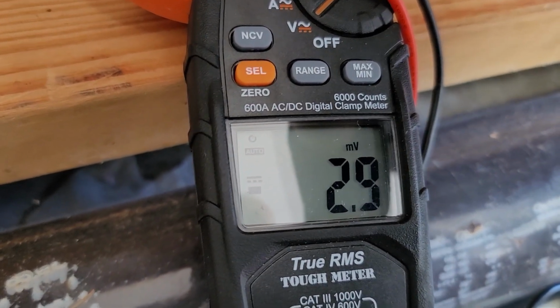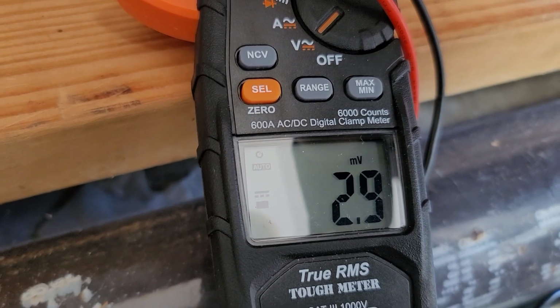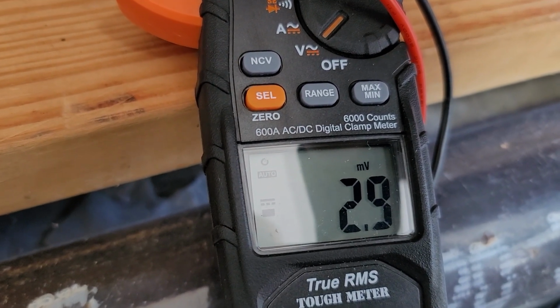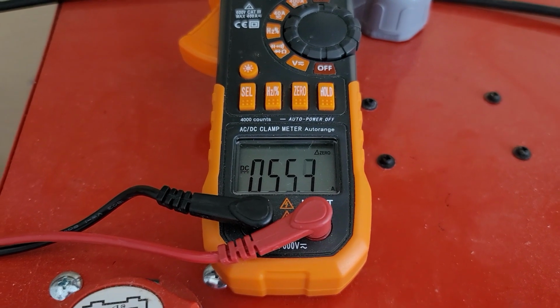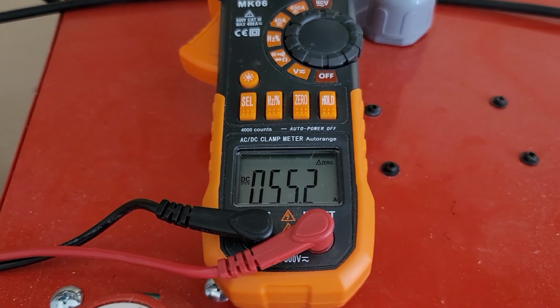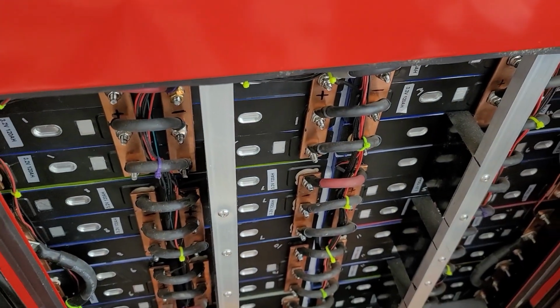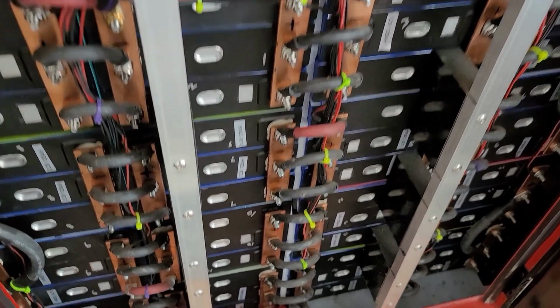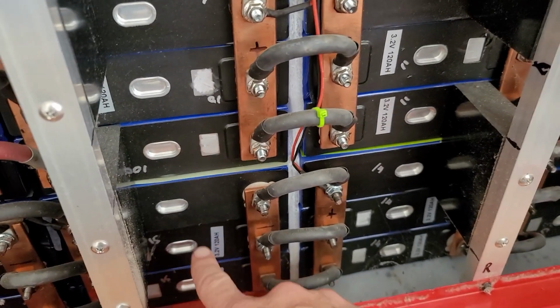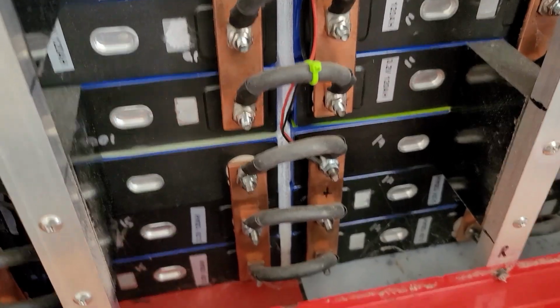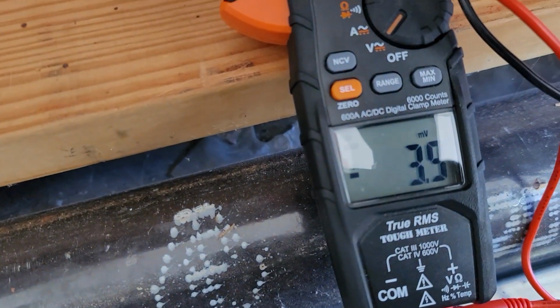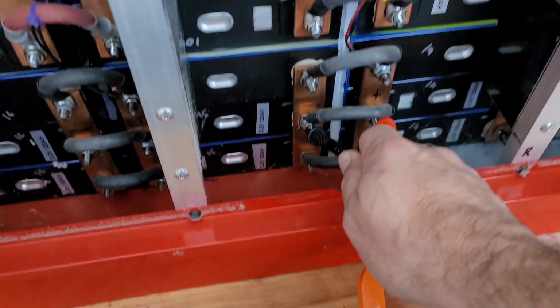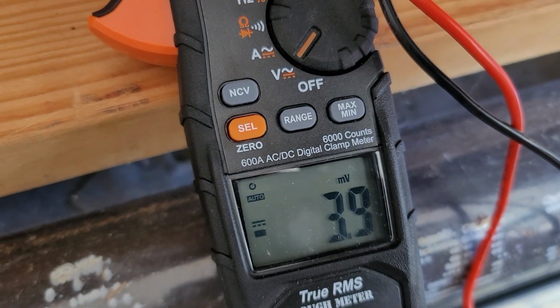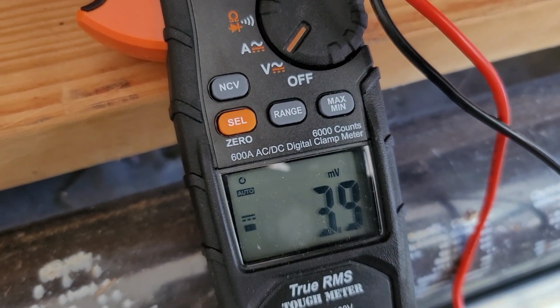As we can see, the voltage drop increases while the charging amperage increases too. Right now we're charging this Powerwall at 55.2 amps, so let's see what the voltage drop is on the connection between modules 14 and 15. Right now, that connection's voltage drop is at 3.9 millivolts.